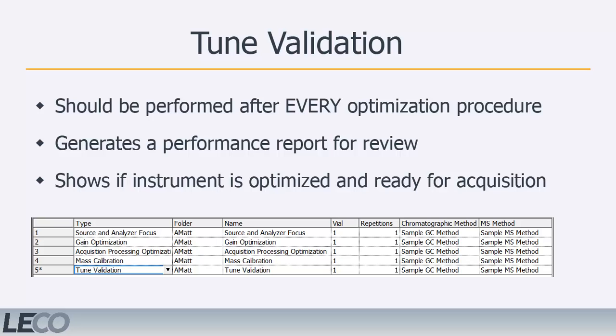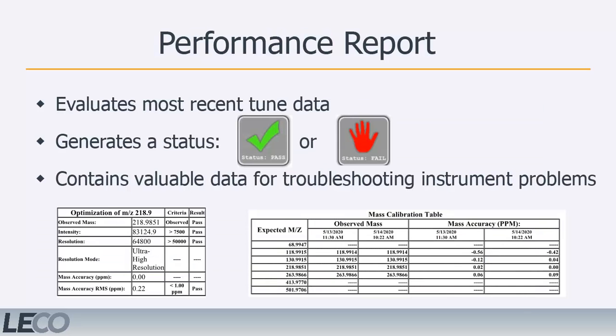The tune validation step collects a small amount of data which will be displayed in the performance report and should be performed after every optimization procedure. The performance report evaluates the tune validation data to determine if the system is ready for sample acquisition. This report produces a status that determines whether analysis should continue or if the instrument requires further attention to achieve optimal performance. It also contains data that can be used to troubleshoot potential problems within the instrument.